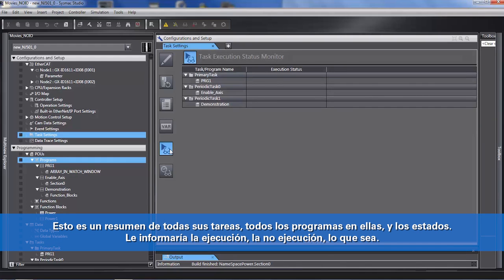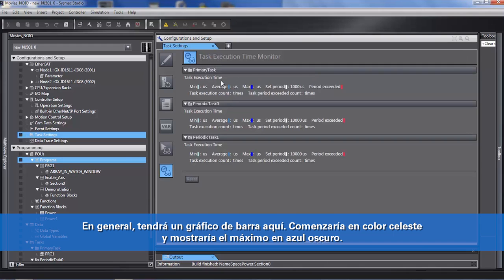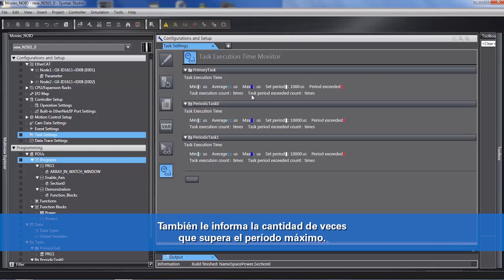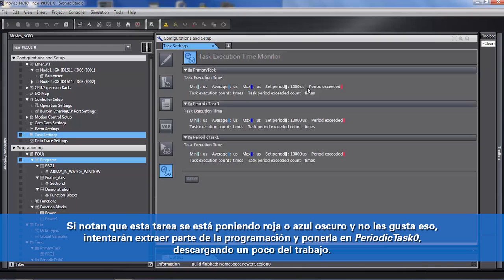This is an overview of all your tasks, all the programs in them, and their status — it would tell you running, not running, and so on. This next view is a bit more important. It normally would show a bar graph that starts off light blue, gets into blue, and shows the maximum in dark blue. It would also turn red if the program could not execute in time, and it tells you the number of times it exceeds the maximum period. Most people put most of the code in the primary task, and if they notice it turning red or dark blue, they will try to extract parts of the code and put it in periodic task 0 to offload some of the work.